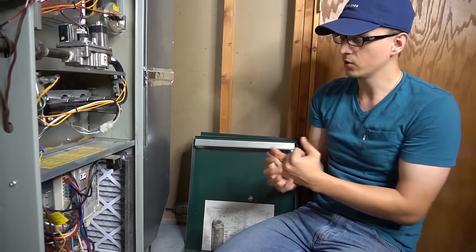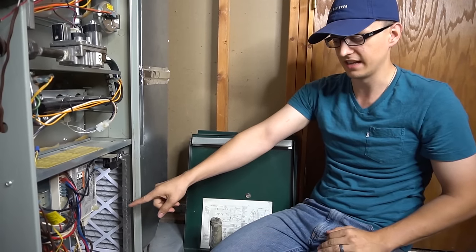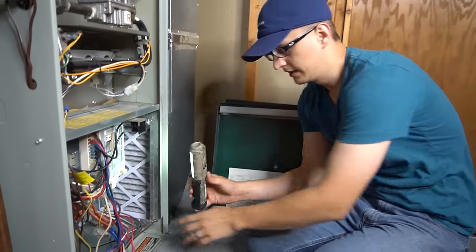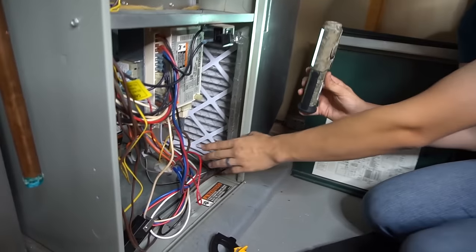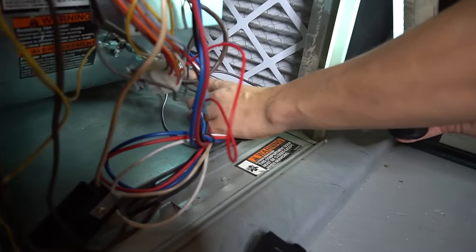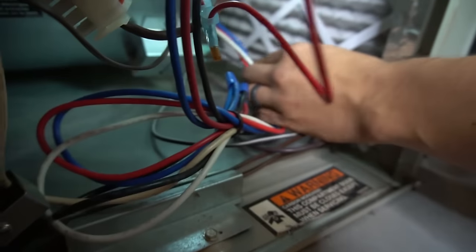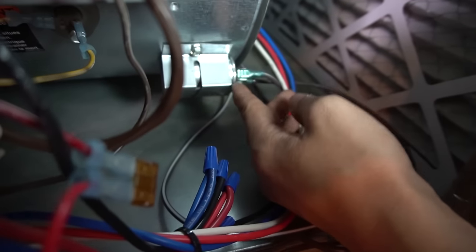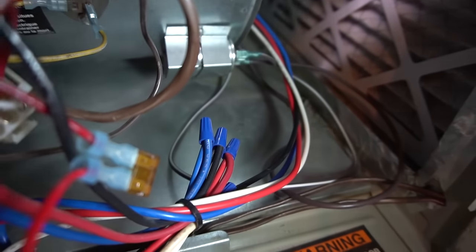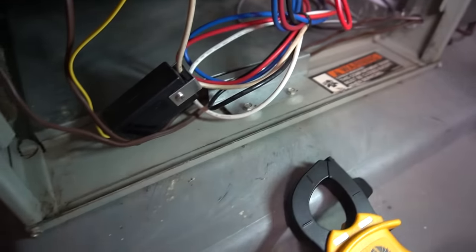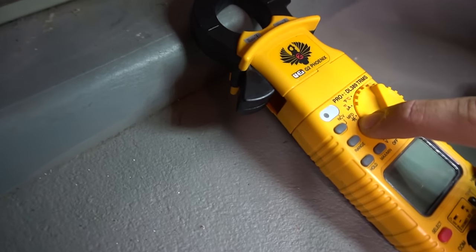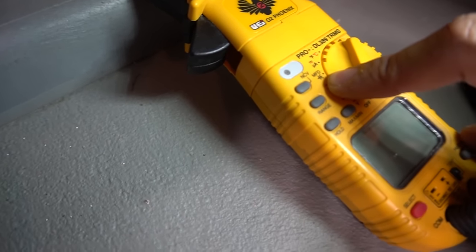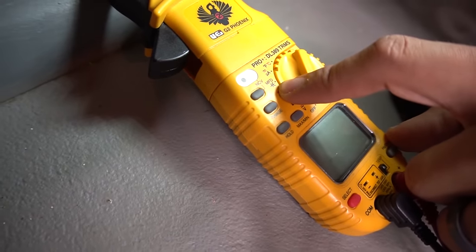Another possibility though, is that your capacitor is actually weak or completely dead. And your capacitor is typically going to be on the motor housing somewhere. Mine, for example, is right here. It's going to be that silver cylinder. So what you want to do is take off the capacitor, disconnect the wires from it, and using your meter on the microfarad selection right here, you want to check the capacitor and see if the rating is matching up the label on it.